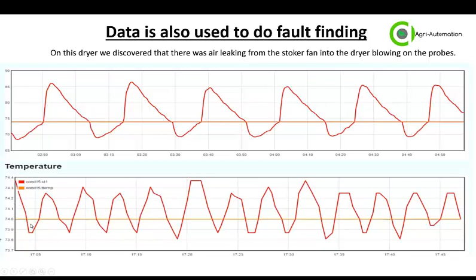We also discovered that one of the dryers had air leaking in from the stoker fan, and it was blowing on the probes. This is the target line, and as you can see, once the line of the actual temperature drops below the target line, it will switch on the fan to push up the temperature, and then it will drop down and eventually turn around and come up. When it stopped, it overshot by almost 10 degrees, and then it will gradually come down. Now, after fixing the leak of air from the dryer, this is the actual slope, and you only have an overshoot of 0.4 of a degree.